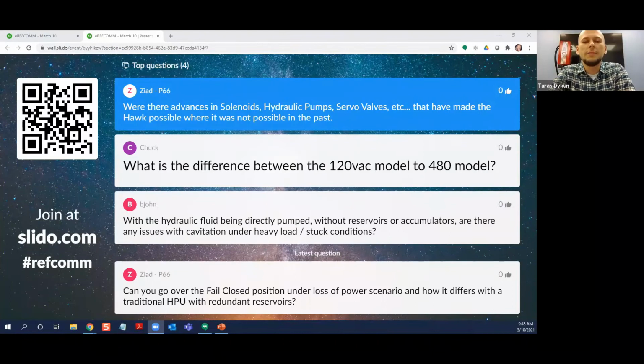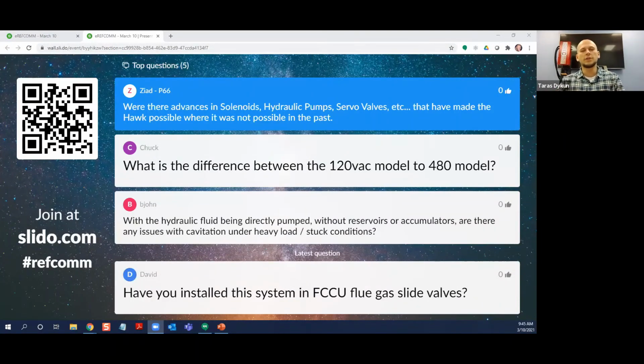So, as my understanding, why there is a way of doing it now compared to why we didn't do it before: one of the things is that solenoid valves used to have quite some delay back in the day. Now we use solenoid valves with 30 to 40 milliseconds opening and reaction time. Sometimes you would build up hydraulic pressure and would not be able to properly control the valve due to the delay of these solenoid valves.